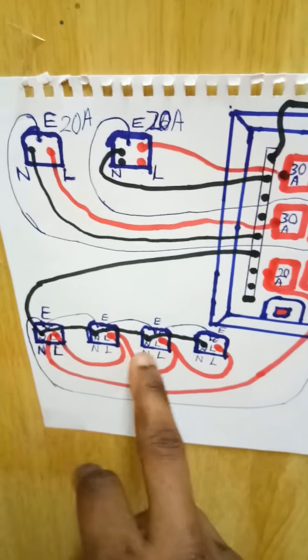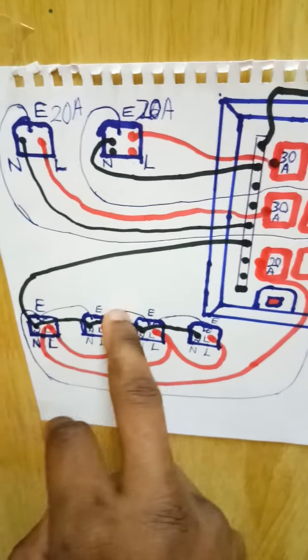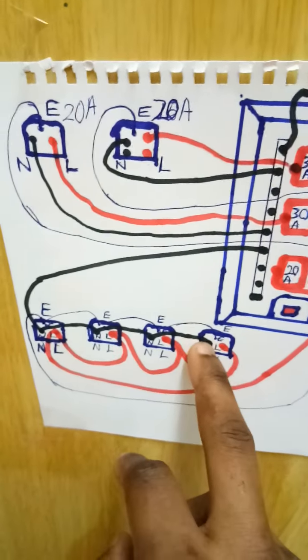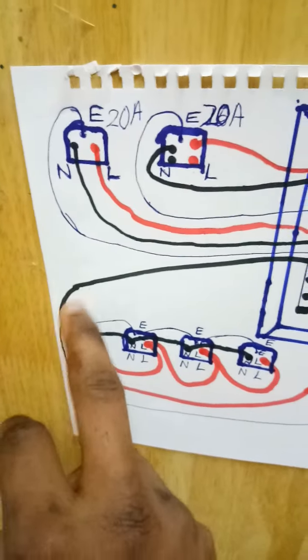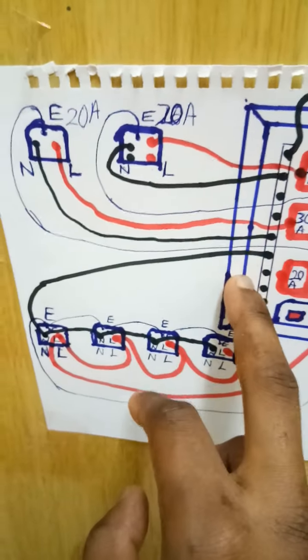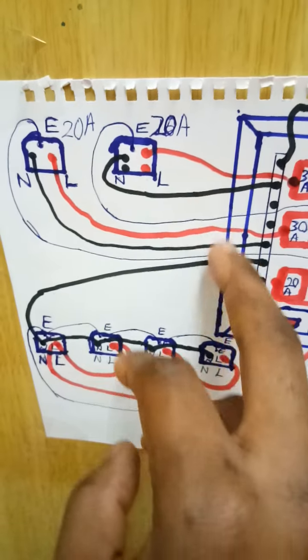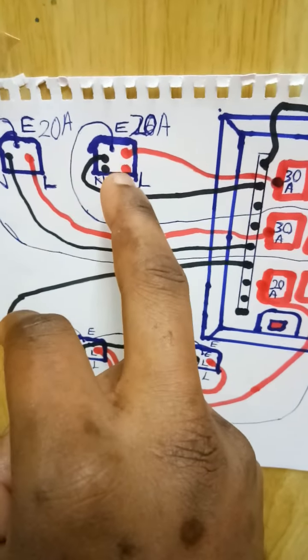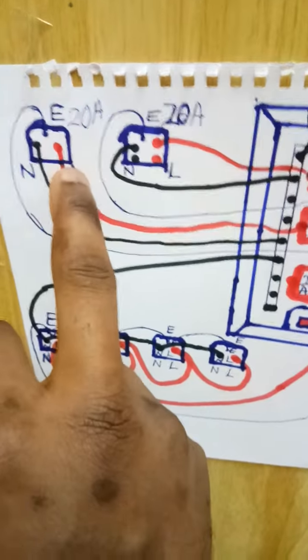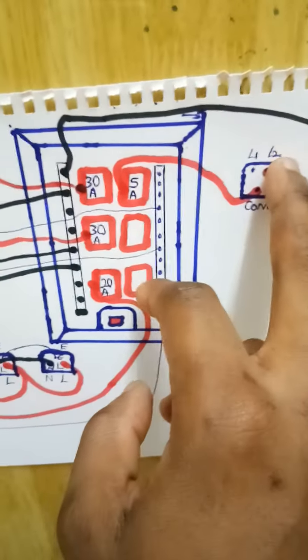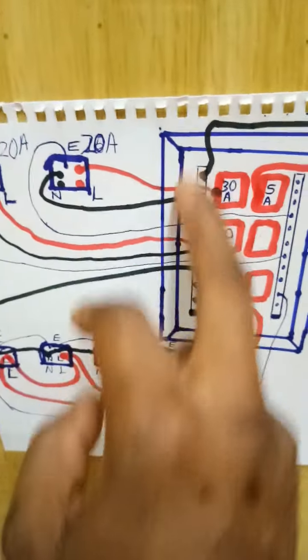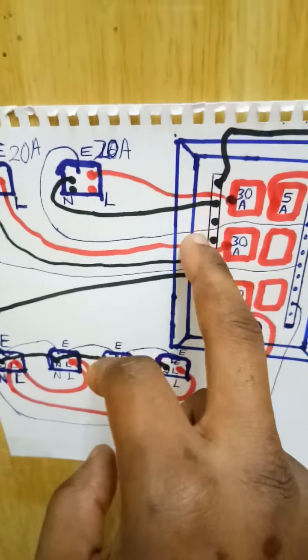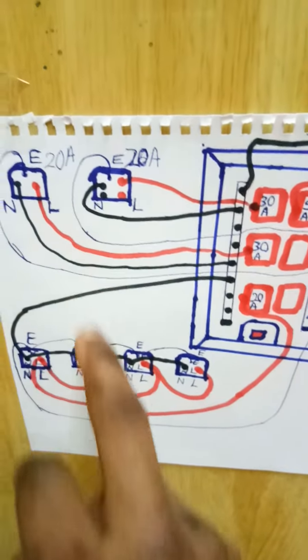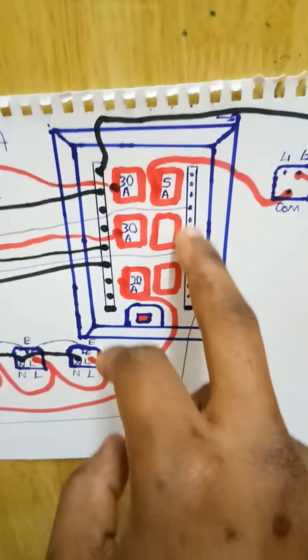As you can see, the live wires join together, all the neutrals join together, and from one point it goes to the neutral rail, where all the neutrals, both from the AC, the water heater, or the lighting point, are coming to this one rail. What you are separating is only the live wires. All the earths are coming to this earth rail.